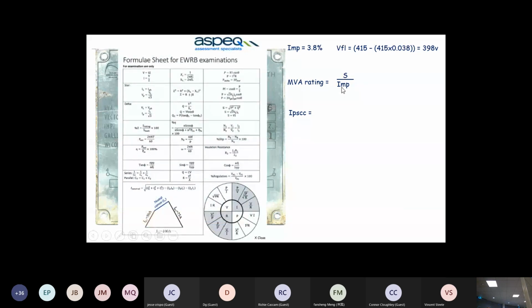Now, if someone wants to borrow some copper and you go to the transformer and that person goes, cut through the copper and you create a dead short, what do you think is going to happen with that kVA? Is it true that that current will not be 278 now? It's going to go much higher, short circuit current. So what's happened with that kVA? It's going to go up as well. Now good guys, you see that formula? Your MVA rating, your fault level rating, is your kVA divided by the impedance.